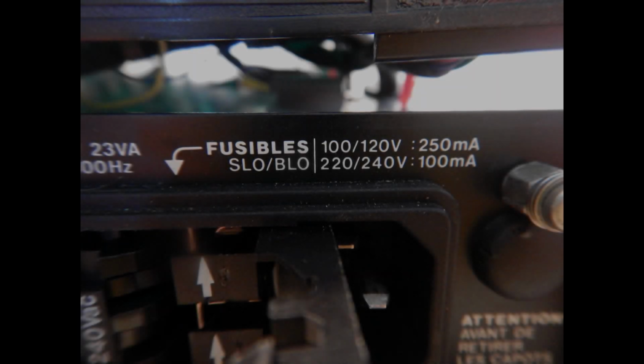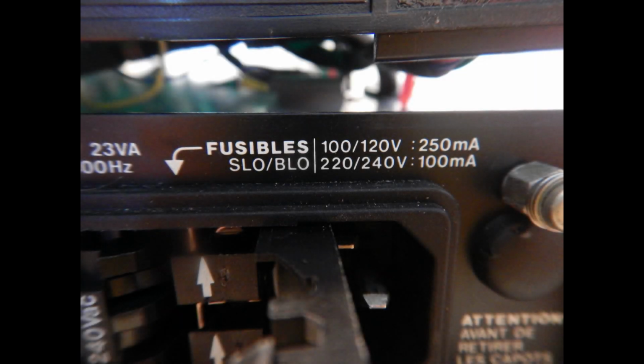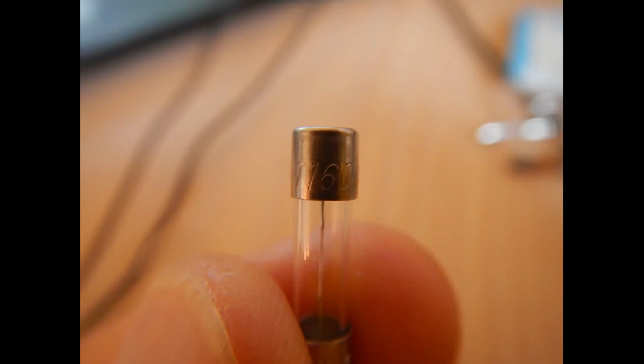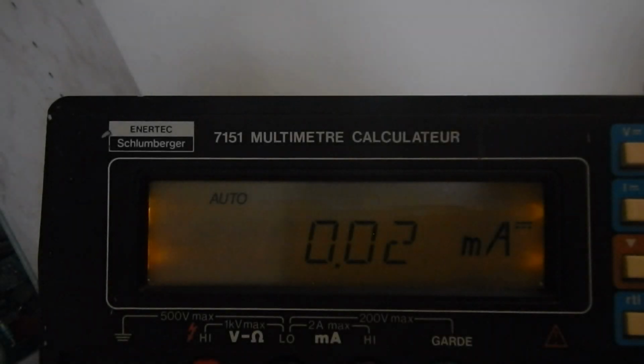Another thing I wanted to check is why the fuse on the transformer primary didn't open. The label says we need 100 mA slow blow fuses for the 240 volt primary. Well, both fuses were 160 mA slow blow, so I've substituted them with the correct ones, but I'm not going to try if they blow with one shorted secondary. However, that didn't change anything.